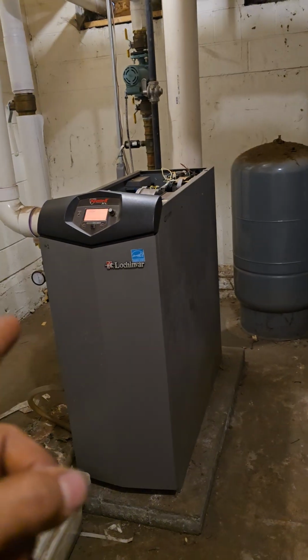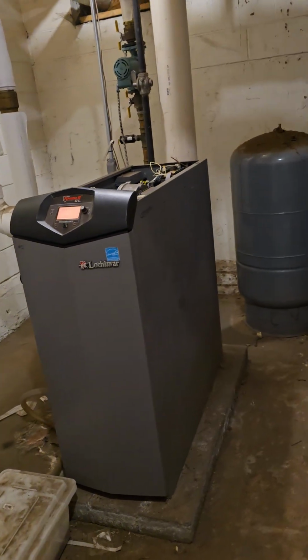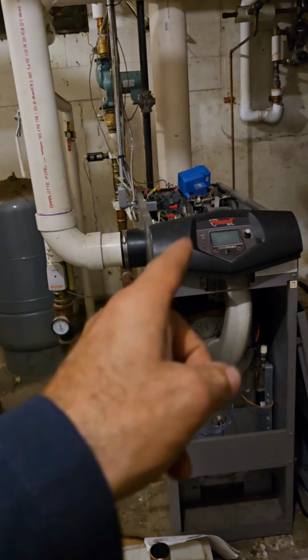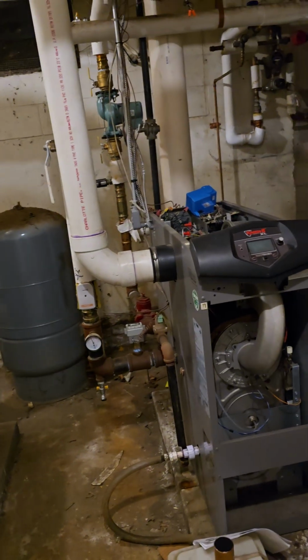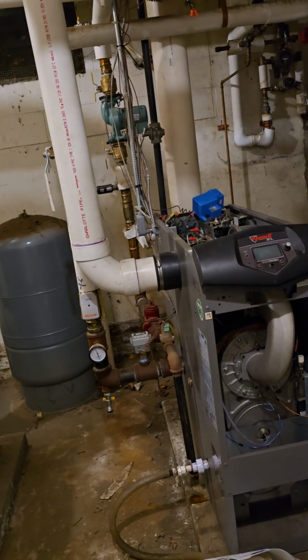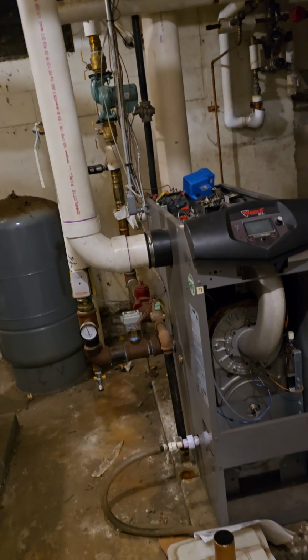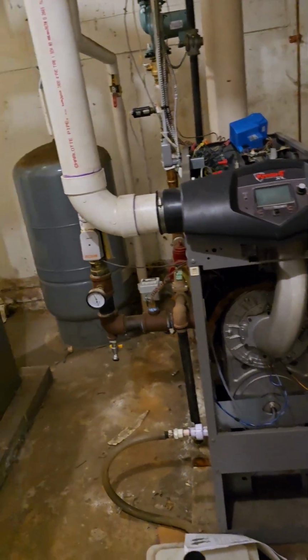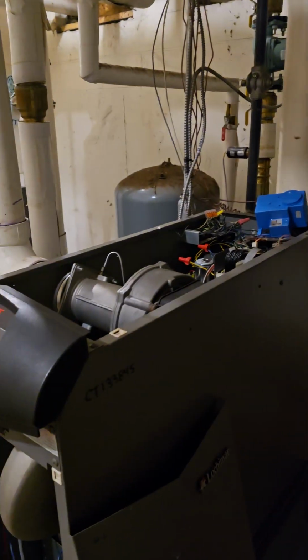This one they jumped out to run a constant set point, which is fine with me. So what I did was I looked, and since this boiler carries our domestic, I had to think why no one else could figure it out. I don't know yet. But what I figured out was if I can have this boiler fire, heat up my primary loop, and somehow get water through this domestic loop on this boiler, it would work.